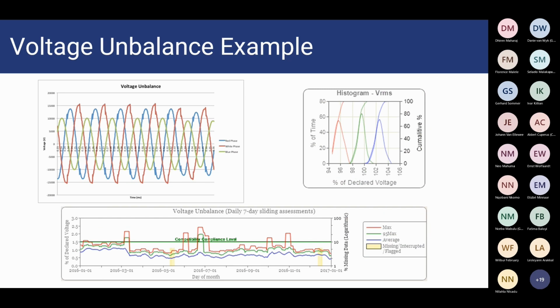Another example here, we have the voltage unbalance being plotted, this time the RMS voltages. We can see the difference in magnitude between the three phases, in the red, white, and blue phase. If we look at the histogram graph that you'll also be able to get from the report generated on Osprey Pro, for most of the time the distribution of your red phase is running at 96%. So it's running well below 100% of the declared voltage. The green phase is on average running close to 100% of the declared, and your blue phase is running high. So you can see the difference in that.